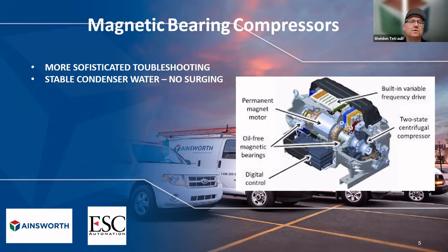They also, as a mechanic, I'll be speaking more as a mechanic than the engineering literature, need stable condenser water, which is pretty important. There are no mechanical thrust bearings, so any of the surging or thrust is handled by magnets, and so surging is detrimental to these machines.